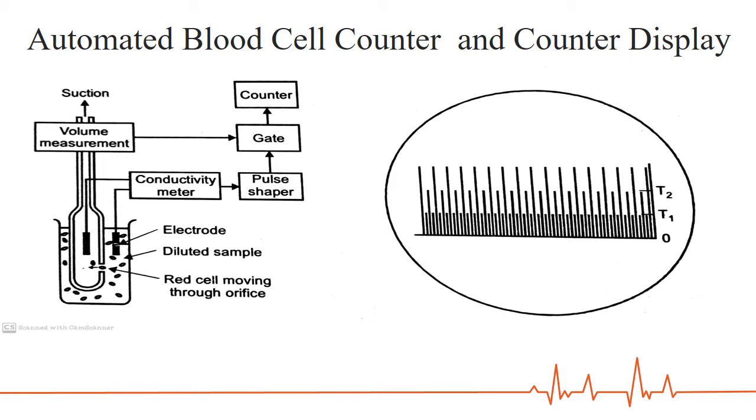The method is based on the fact that red cells have higher electrical resistivity than the saline solution in which they are suspended. Here, we will be able to see the automatic blood cell counter using an electronic circuitry. A diluted blood sample is drawn through a small orifice having diameter less than 100 micrometers by means of a suction pump.